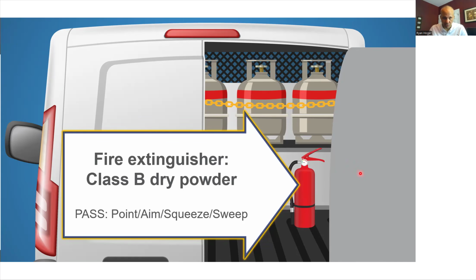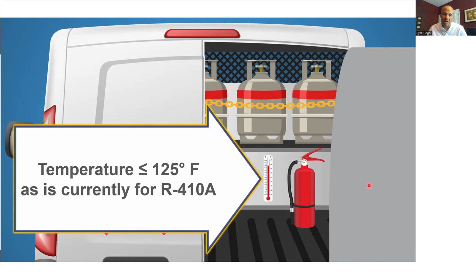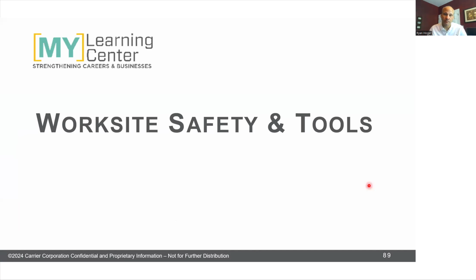All right, you have to have a fire extinguisher on your service van. You're already required to have that. You're supposed to already have that anyway because you have other flammable things like acetylene on there. So that's not new. You just got to do it. You're not supposed to have your van above 125 degrees. That is already the current rule for R-410A, so that is not a new rule either.